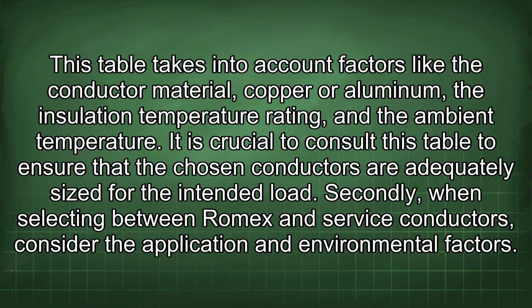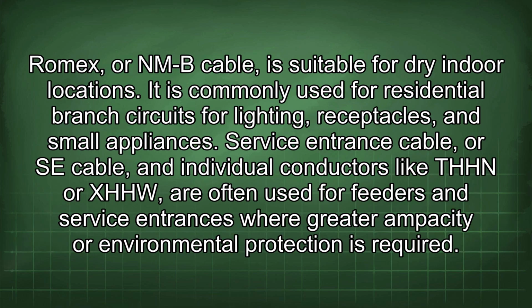This table takes into account factors like the conductor material, copper or aluminum, the insulation temperature rating, and the ambient temperature. It is crucial to consult this table to ensure that the chosen conductors are adequately sized for the intended load. Secondly, when selecting between Romex and service conductors, consider the application and environmental factors. Romex or NMB cable is suitable for dry indoor locations. It is commonly used for residential branch circuits for lighting, receptacles, and small appliances.